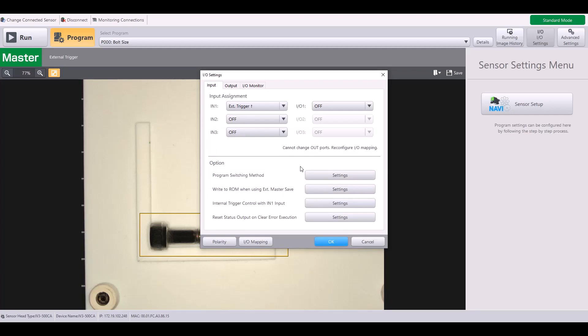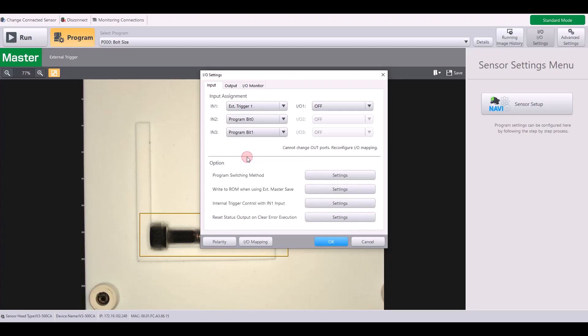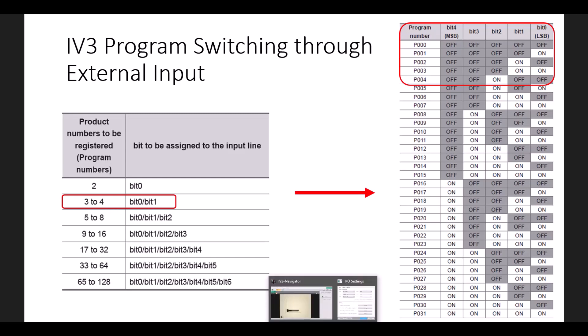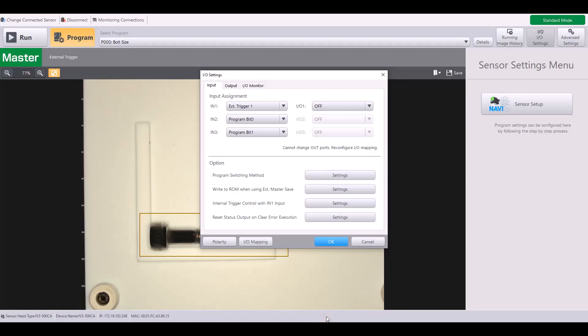And so now I need to assign my input lines. My input two, I'm going to use bit zero. Input three, I'm going to use bit one. And again, this is because I'm switching between a total of four programs. So those are the two change bits I need to be using. You can hit OK here.